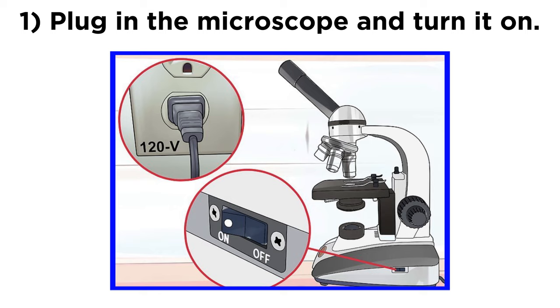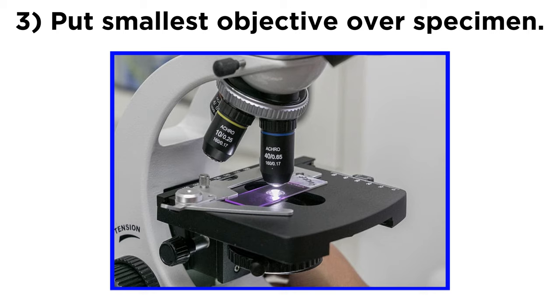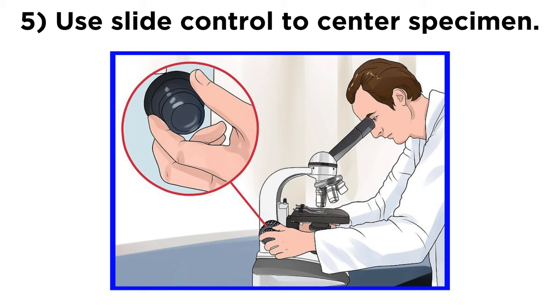To put these parts to use, one can start by plugging the light microscope in and turning on the light source. Then secure the specimen on the stage using the stage clips, before rotating the nosepiece so that the smallest objective is in place over the specimen. First use the coarse focus knob to clear up the image, then use the slide control knobs to center the specimen in your field of view.